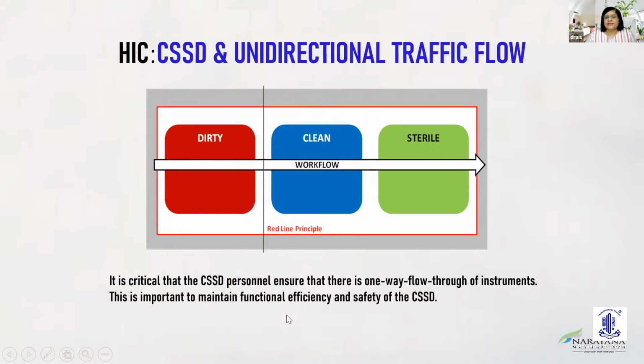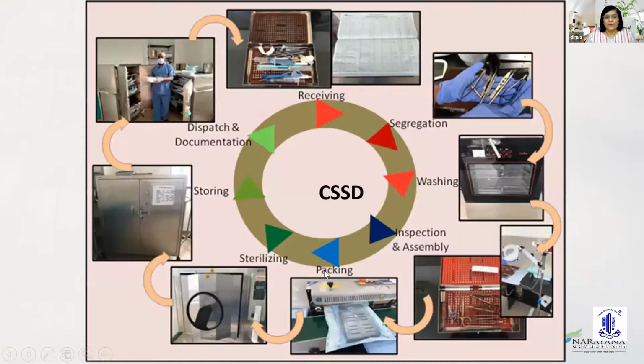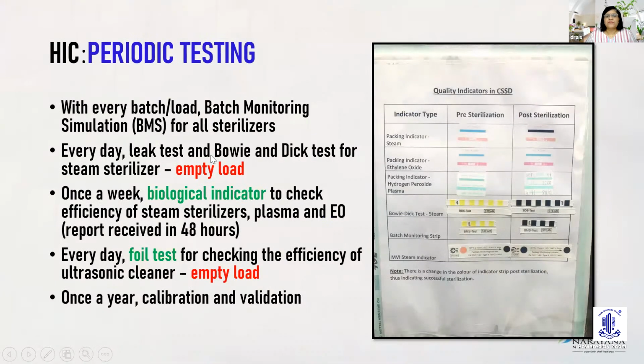This is critical for the CSSD personnel to ensure that there is one-way flow through of instruments, and it is important to maintain functional efficiency and safety of the CSSD. No matter how the OT is designed, this protocol should be regularly followed. I would like to just take you through how the CSSD functioning happens. For example, when the segregation of the instruments has happened, the washing happens, then the inspection and assembly takes place, then the packaging takes place, then the sterilization happens, storage happens, and then the dispatch and documentation takes place.